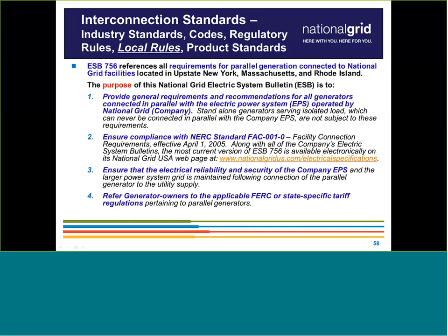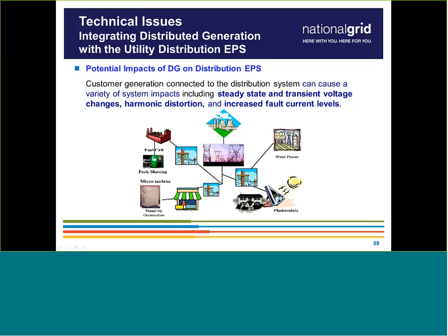Here's a short, abbreviated list of what we look for in our system impact studies — things we want to mitigate: steady state and transient voltage changes, so we have a load flow model we'll look over, and a short circuit model where we look for increased fault current levels. We make sure relays aren't getting desensitized, and we look at overcurrent protection throughout the system, from the substation down to your own generator.